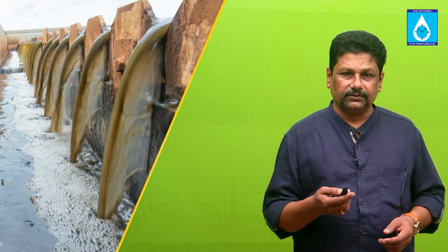So I'll also give you a brief about what we have been talking visually to you, so that you understand about the start, stops, and center to center distance, the benching, and what should be. Many people ask me, like, where should I put the sewage pump? Can I put it right on the floor? No, please don't put that right on the floor, because you are not allowing space for the pump to suck what it needs to do. So you need to put it a little up. What is that little up? I always say it should be minimum 100 mm or half the diameter of the volute, whichever is higher.